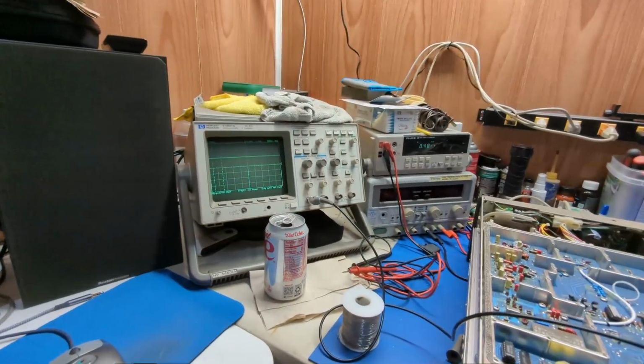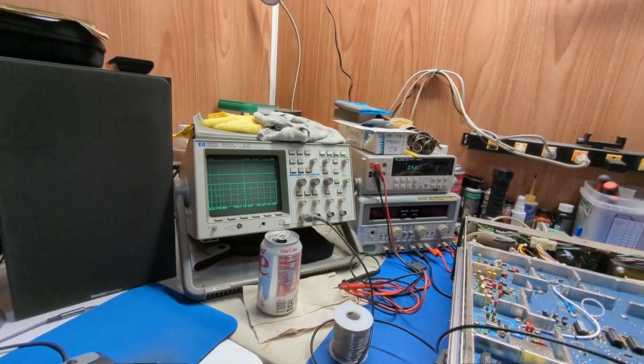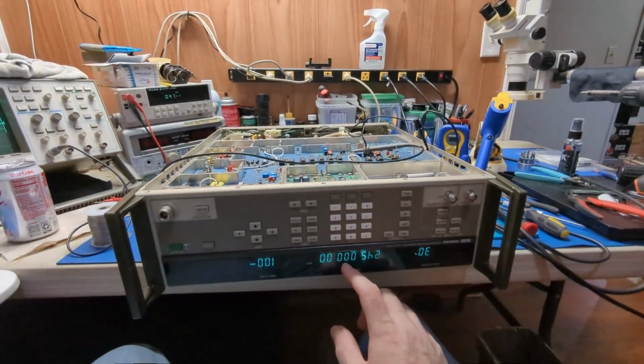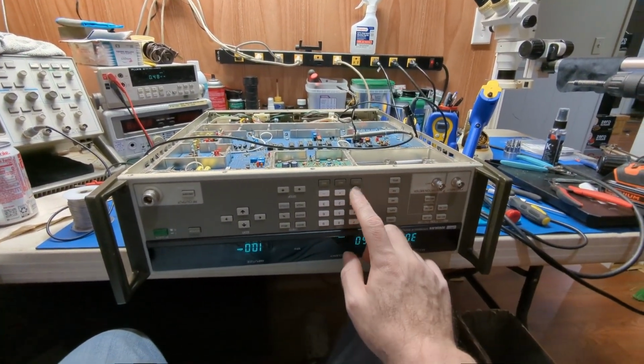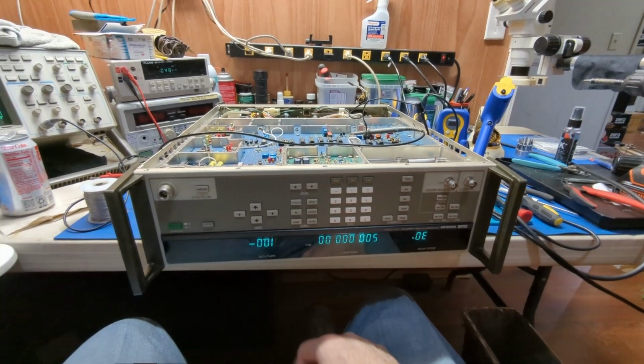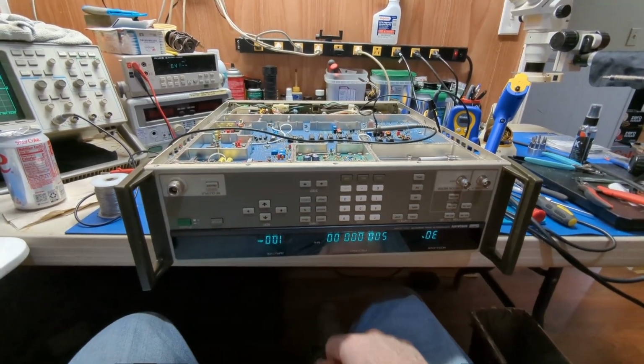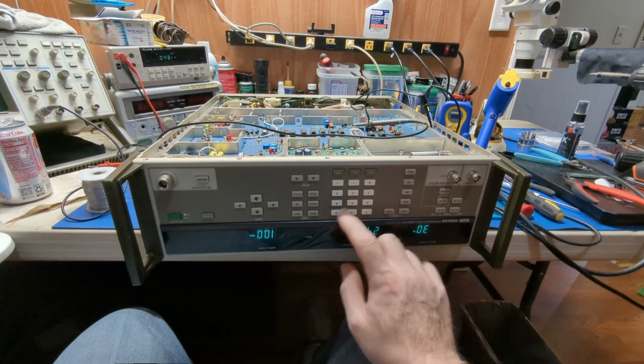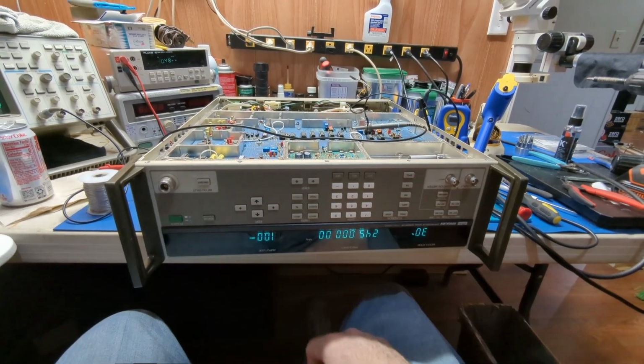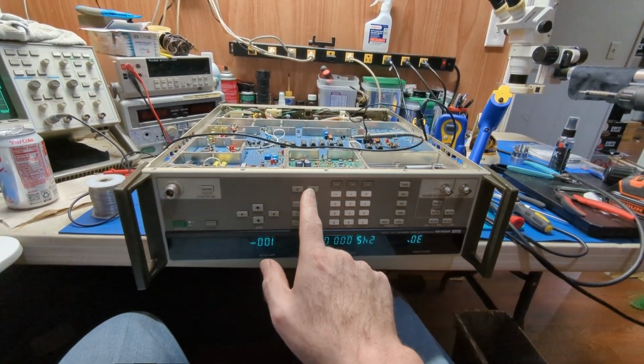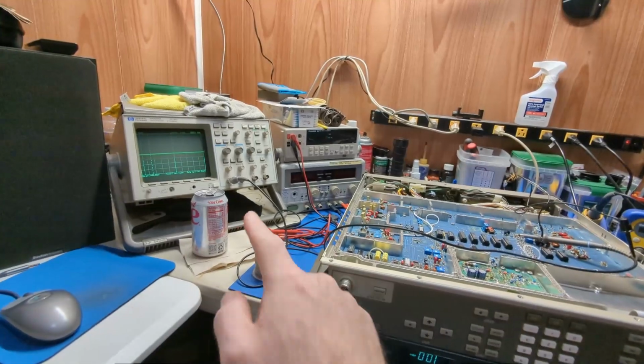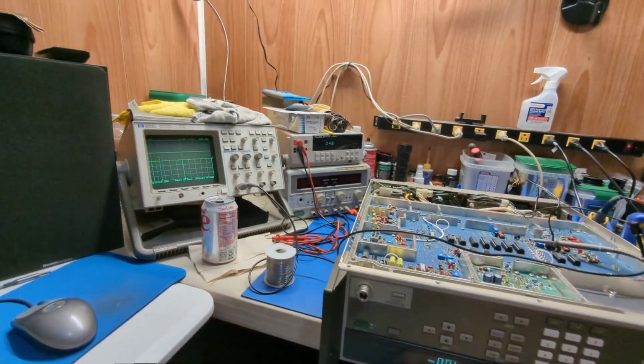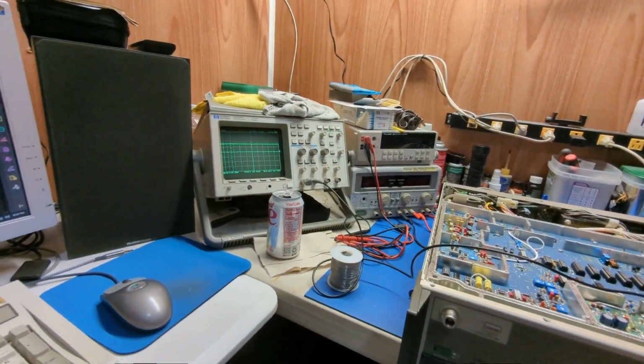So the mid band and high band is working fine. Like I can go to the high band right now, 500 megahertz. High band works fine, no errors. So 245 goes right back to the mid band. And as soon as I go down 1, takes us to the low band, and I lose the pulse or the output level from the detector diode.